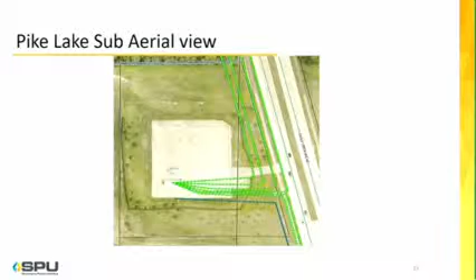At Pike Lake, going back to the image for Pike Lake, we see that we have the room to add a second lineup right here with another tap. So the transmission line is tapped, it goes in, comes back out, so it's looped. And then there's a breaker, and then there's our transformer, and then there's our 15 kV switchgear, which is our distribution voltage, and our underground exit circuits. We could have a second line up here, and when there's a second line up here, this could be an automated process, should there be an outage from one direction or the other, to re-energize both of the transformers there.